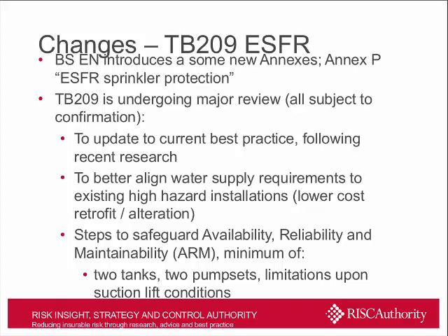And we'll be taking the usual steps to safeguard availability, reliability, and maintainability. For example, we'll be specifying a minimum of 2 tanks, 2 pump sets, and that limitations upon suction lift conditions should apply in the case of the ESFR protection.